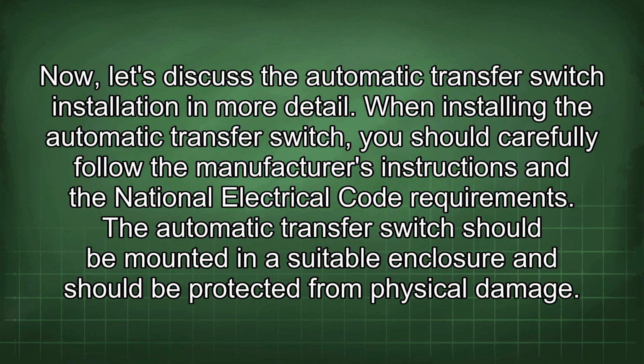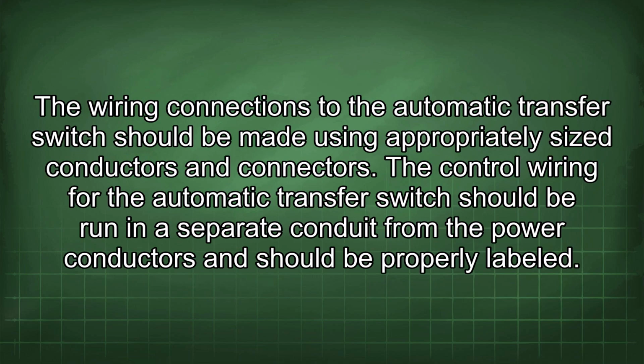Now, let's discuss the automatic transfer switch installation in more detail. When installing the automatic transfer switch, you should carefully follow the manufacturer's instructions and the National Electrical Code requirements. The automatic transfer switch should be mounted in a suitable enclosure and should be protected from physical damage. The wiring connections to the automatic transfer switch should be made using appropriately sized conductors and connectors. The control wiring for the automatic transfer switch should be run in a separate conduit from the power conductors and should be properly labeled.